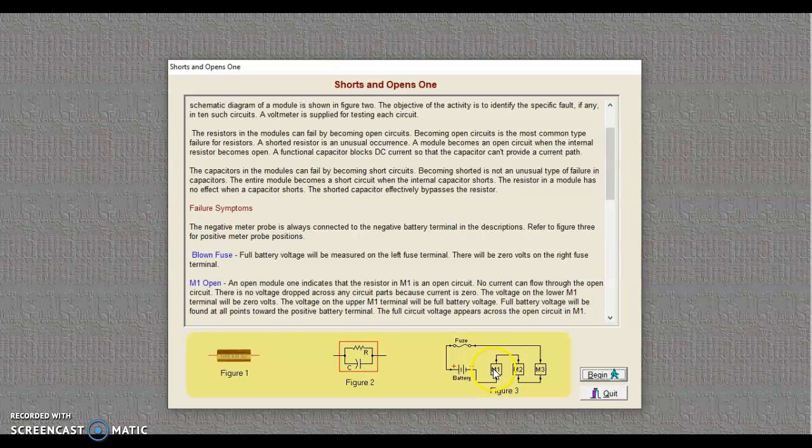If one of these were shorted, what we would see is about a 6-volt drop at the other two modules because a shorted module doesn't see any load voltage on it. So let's begin this and see what happens.